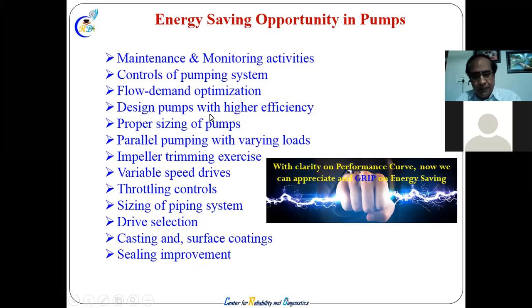Maintenance and monitoring opportunities, controlling systems, operation, flow demand, design of pumps, other efficiency measures, proper sizing of pumps. If it is already shipped, we have to size it properly, and that time it comes down to maintenance only. Otherwise it is good if the engineering group takes care and gives me equipment which is energy efficient. So parallel pumping and other things, these are all maintenance and operational issues, impeller trimming, velocity, all the things where you can save energy in pumps.